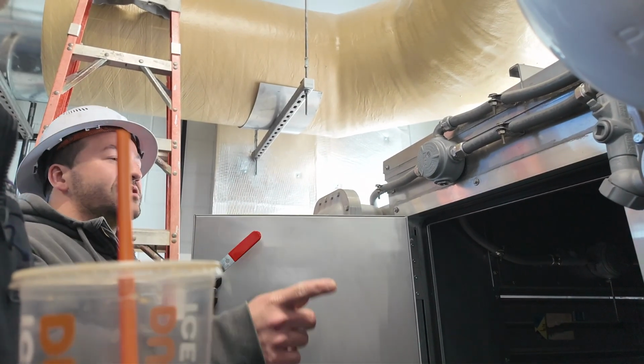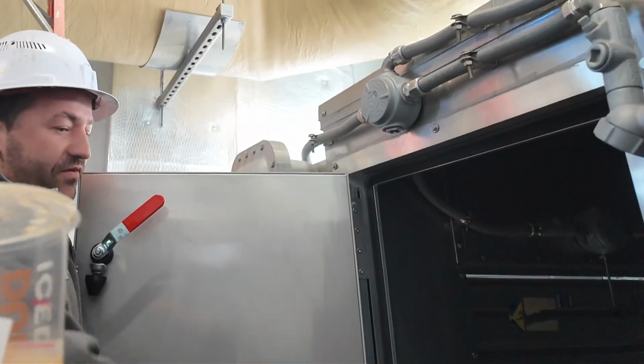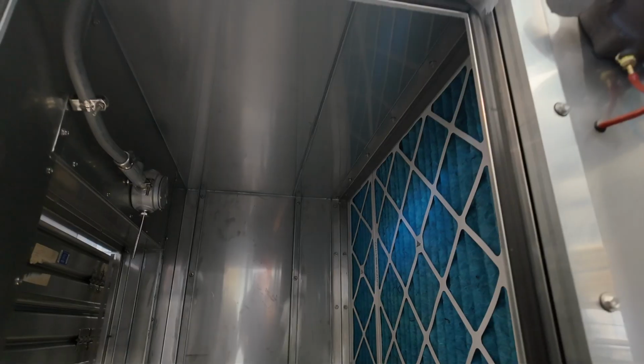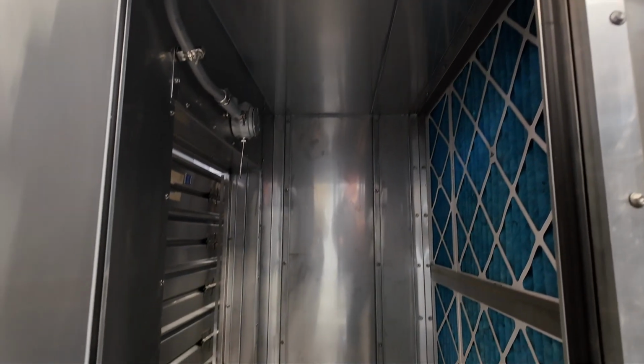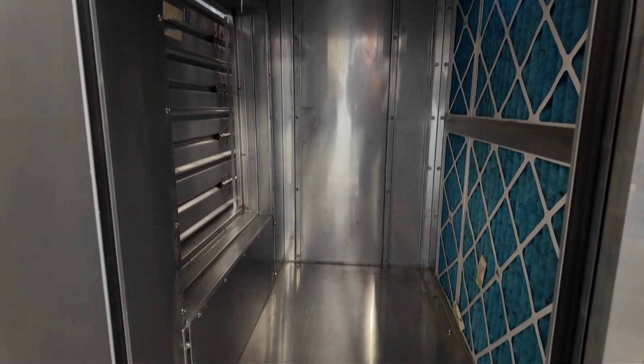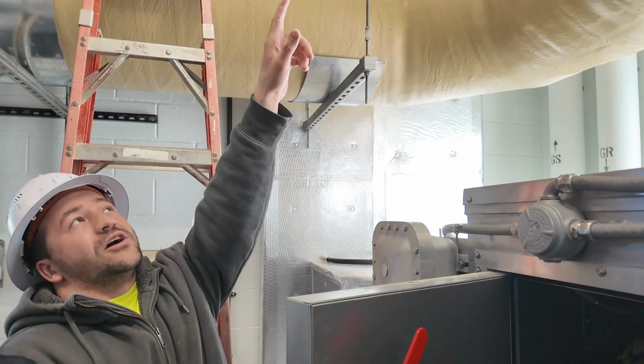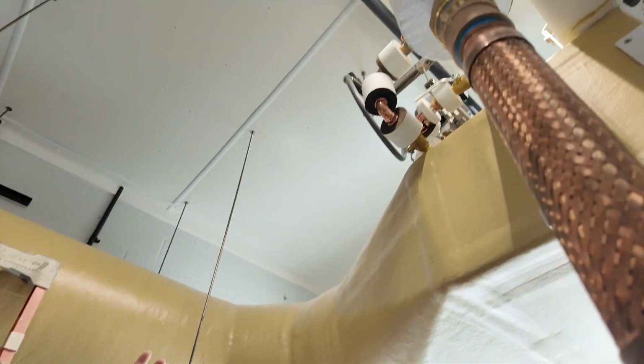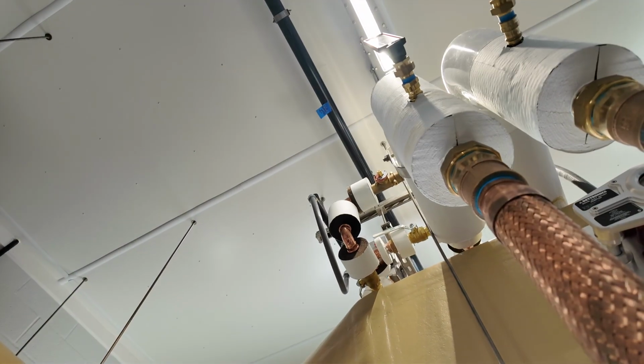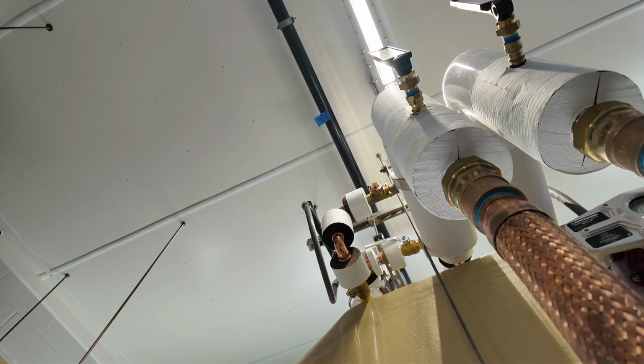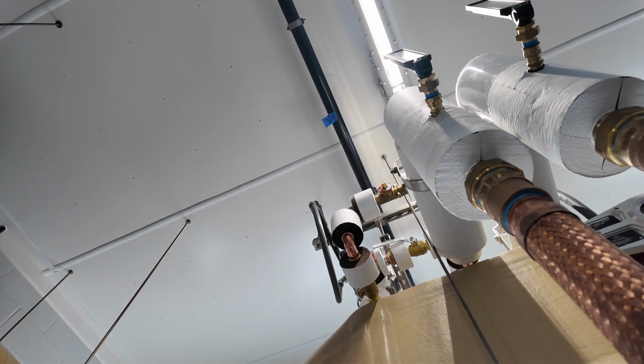And if the coil ever gets dirty, clean it. Just pop out those filters, wash it off with anything that's not corrosive, Dawn dish soap or something like that, to degrease it a little bit, with some water. This is your actuator. That's your hot water valve. That's the indicator arrow right now. It's closed, system's off. Once the valve's actually open, that dial will start to move. Straight up, pointing up, would be 100% open.